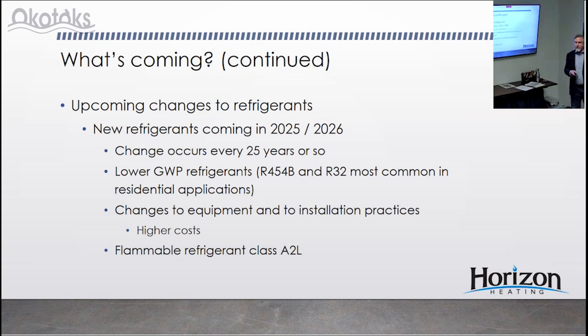So what's the net effect? The net effect is that this new refrigerant is in a new class of mildly flammable refrigerants, so they have to be handled differently. Installation practices are a little different. There's no real risk if everything is done correctly. There's a little bit of panic out there when people hear mildly flammable, but when you think about it, probably all of our homes have a gas line coming in, which is more flammable than these refrigerants. So there are safeguards, safety checks, and leak detection systems built into these systems now, which weren't built into the old systems because we didn't need them.